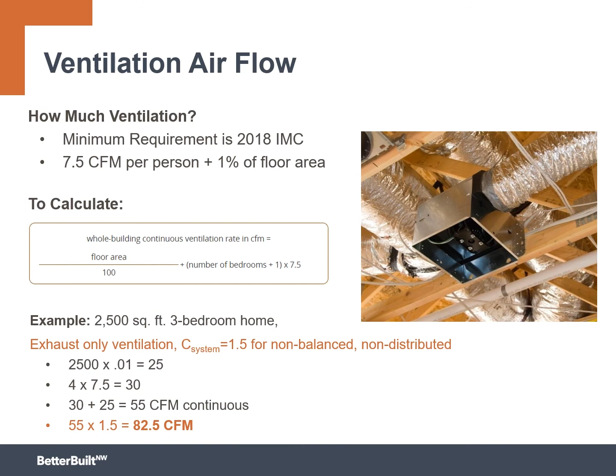But remember I said earlier, there's a benefit to doing balanced ventilation. This is where that kicks in. For a home that's neither balanced nor distributed, you have to multiply this by a ventilation adjustment factor, right? And it's 1.5 for something that's neither balanced nor distributed. So all of a sudden, a fan that needed to be 55 CFM continuous now needs to be 83 CFM continuous. You see the challenge here? By choosing to go with exhaust only, you now have to do more ventilation. So it changes the size of equipment you buy. You have to decide, am I going to achieve that with 1 fan, 2 fans, 3 fans? It does make your life a little bit more complicated.